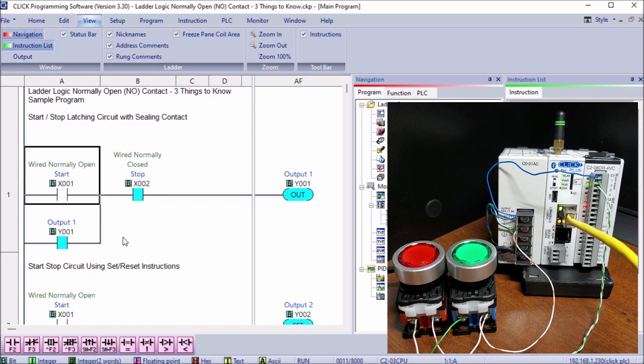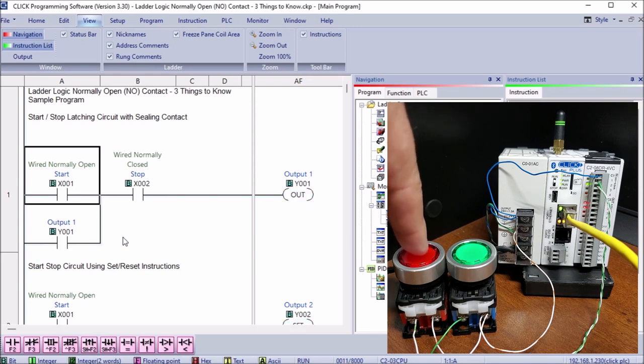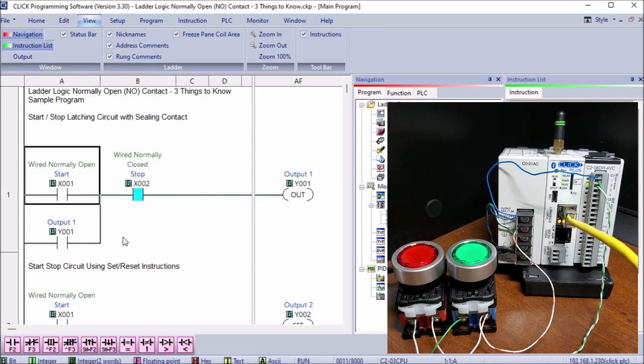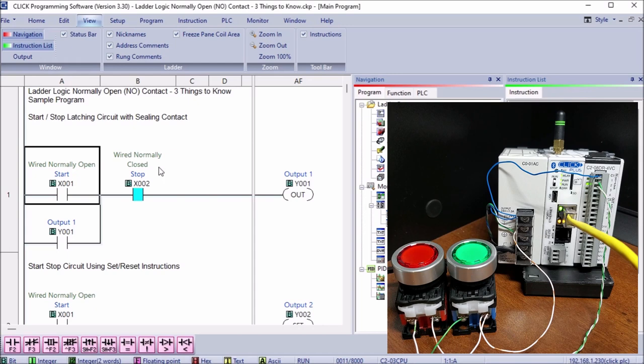I let go of the start - you can see that it maintains it because of that latch. If I want to stop it, I hit the stop button. It breaks that circuit and then stops it. Let go of it and again it activates X2 because of the normally closed wiring, even though it's showing normally open contact on our ladder logic.